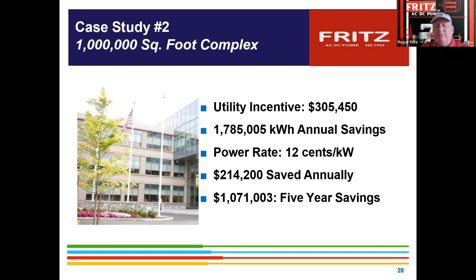This happened to be about a 1 million square foot facility. When we first walked in, they said, oh, we've got drives on. Yeah, they did, everything above 30 horsepower. About 100 motors later found in the facility, incentives were about $305,000, and a couple hundred thousand dollars in annual savings. So it's definitely good. Heidi came up with the concept of being a motor hunter. They're all hidden in the walls and back rooms, and people don't necessarily see them every day. They feel the fans and the cooling going on in the building, but they don't necessarily see it. Or in a production facility, I have to have that machine running.